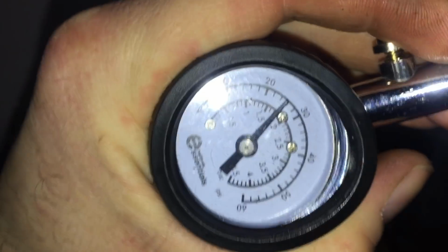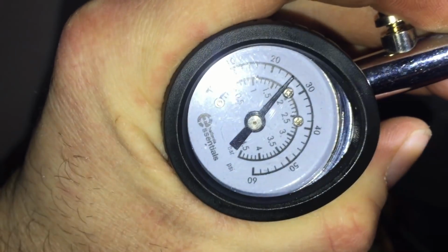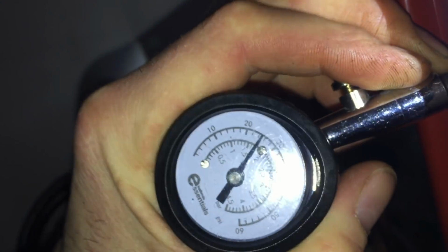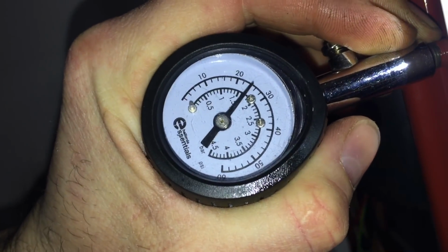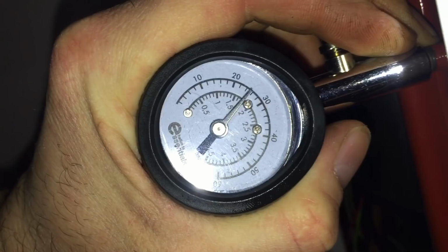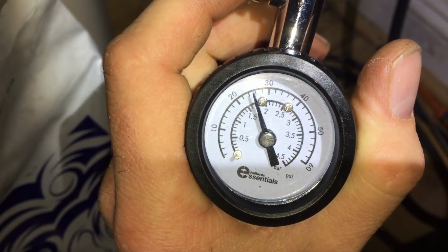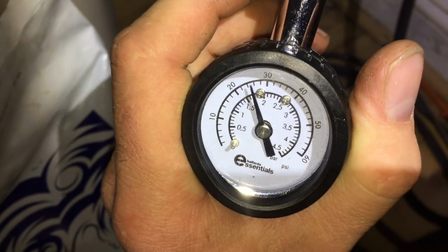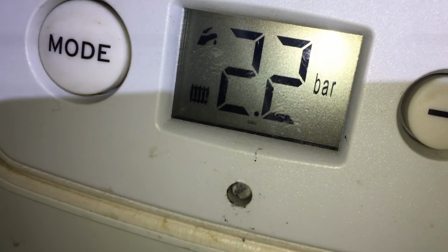So this is the boiler all back together now, and it is working, and you see that expansion vessel pressure is now up at over 1.5 bar. It's about 1.75 bar, and that's because this boiler is on and running now. So the water within the system has expanded slightly, and it's pressing against that. So look, this boiler is now at 2.2 bar.